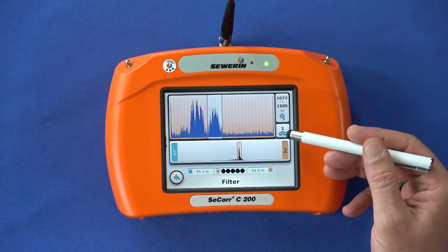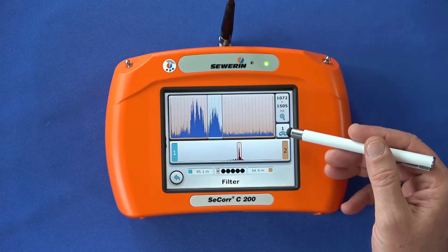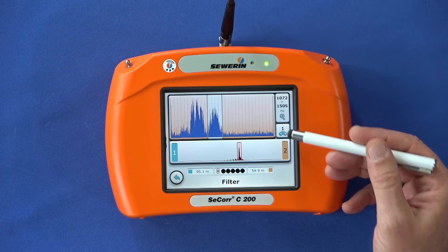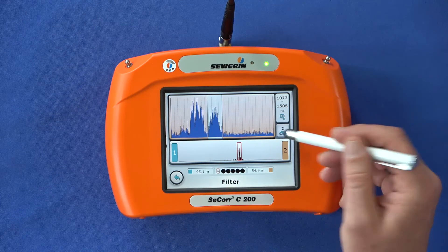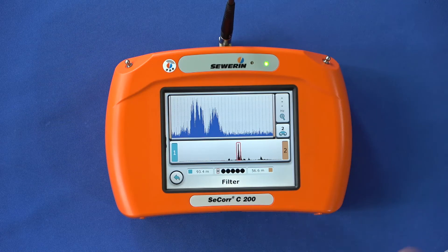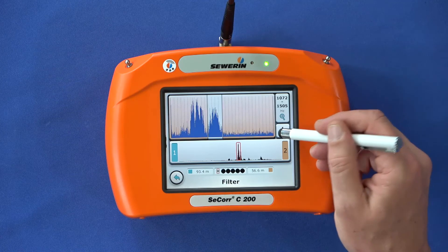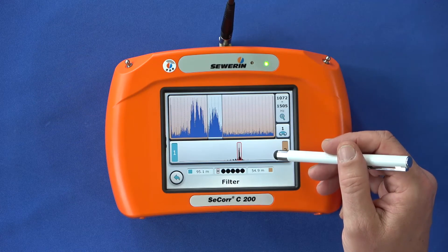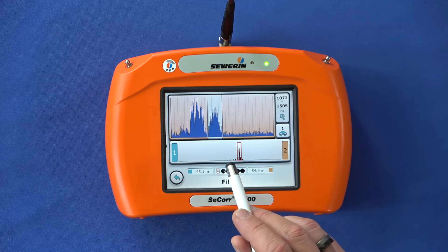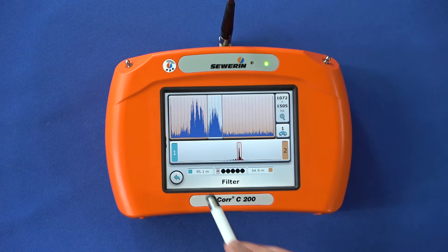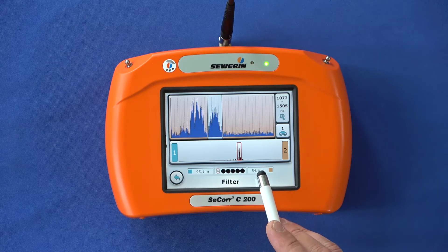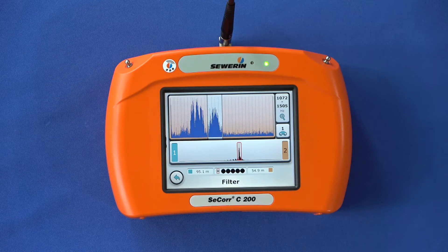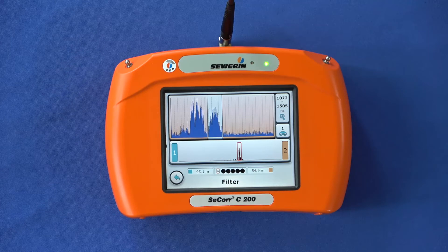To the right of the graphic you can see the currently selected filter limits on a button, and below that the information about the current autofilter 1. If you tap this button you will see autofilter 2. Tapping again takes you to the manual filter, so you can always switch between the autofilters and the filter you have set manually. Below the filter base you can see the correlation function — it is always recalculated immediately based on the selected filter. Below you will find the corresponding result information: the distances from both measuring points as well as the calculated quality of the peak. This gives you the opportunity to assess the effects of filters at a glance.